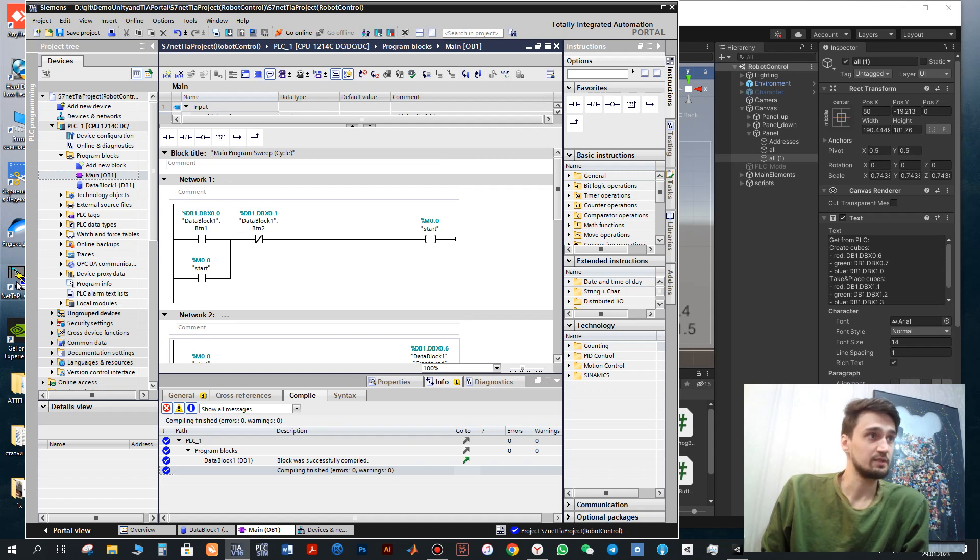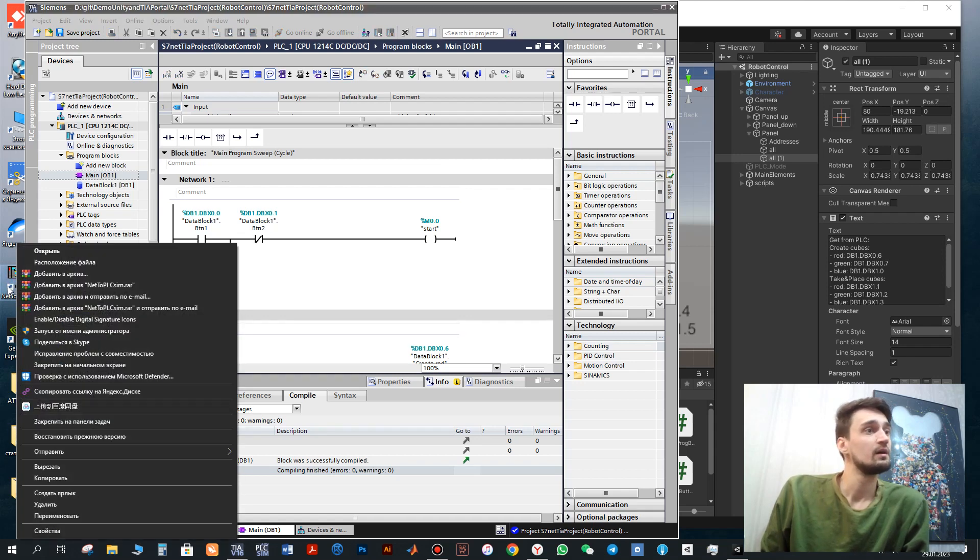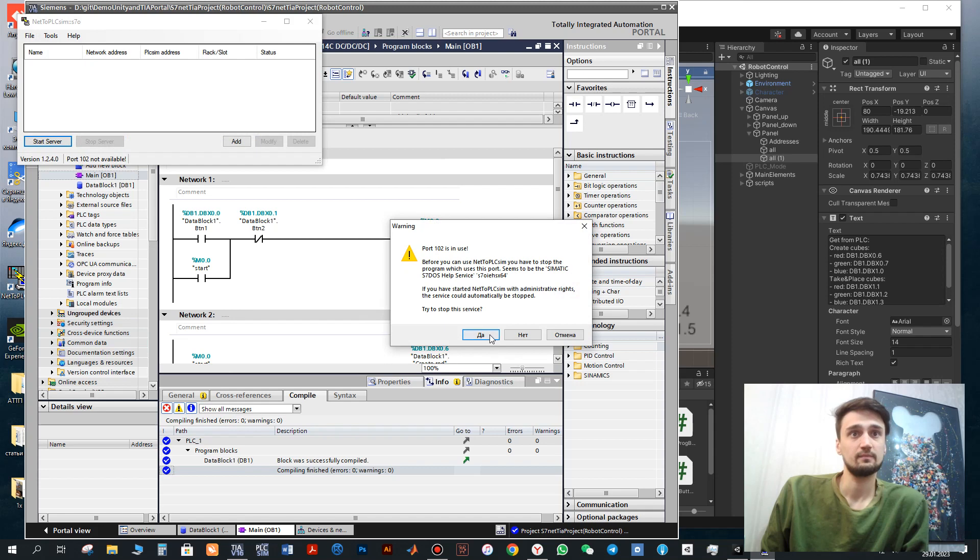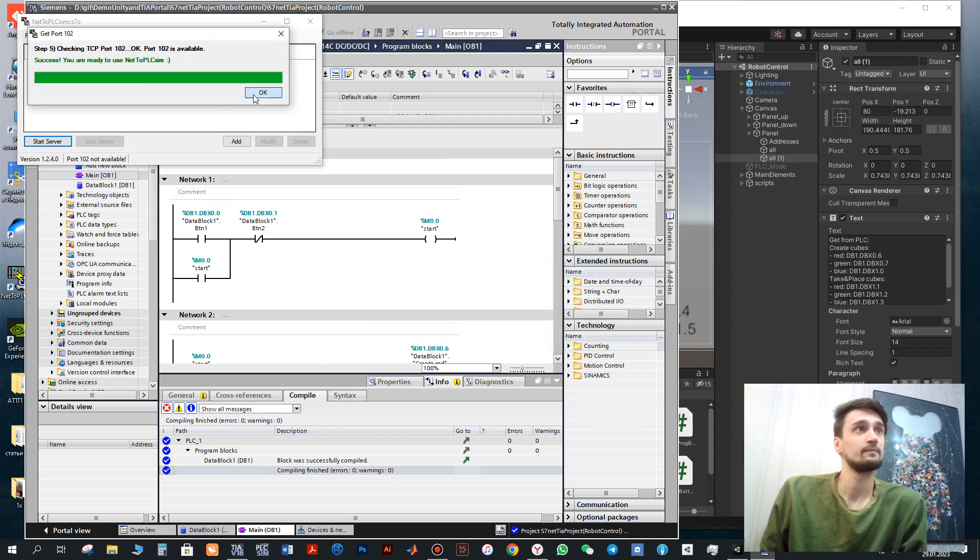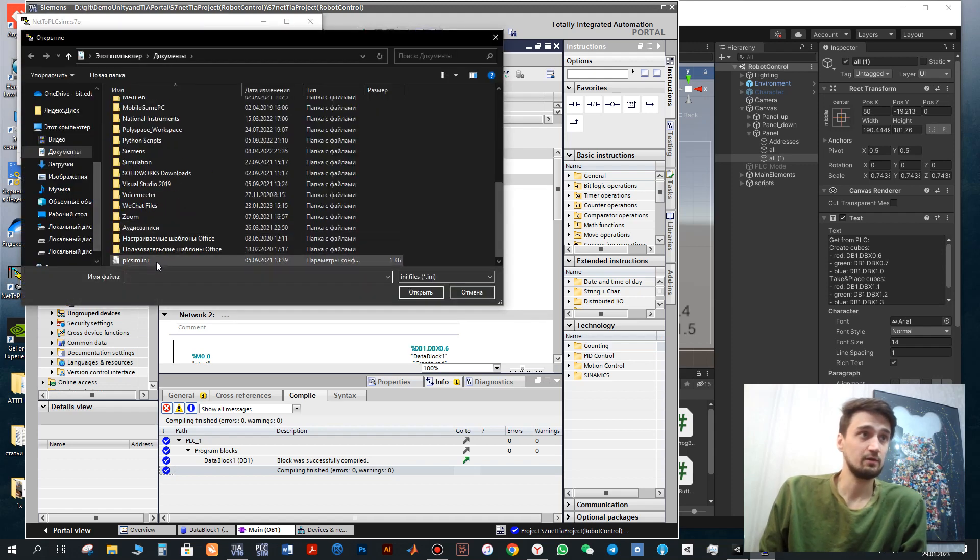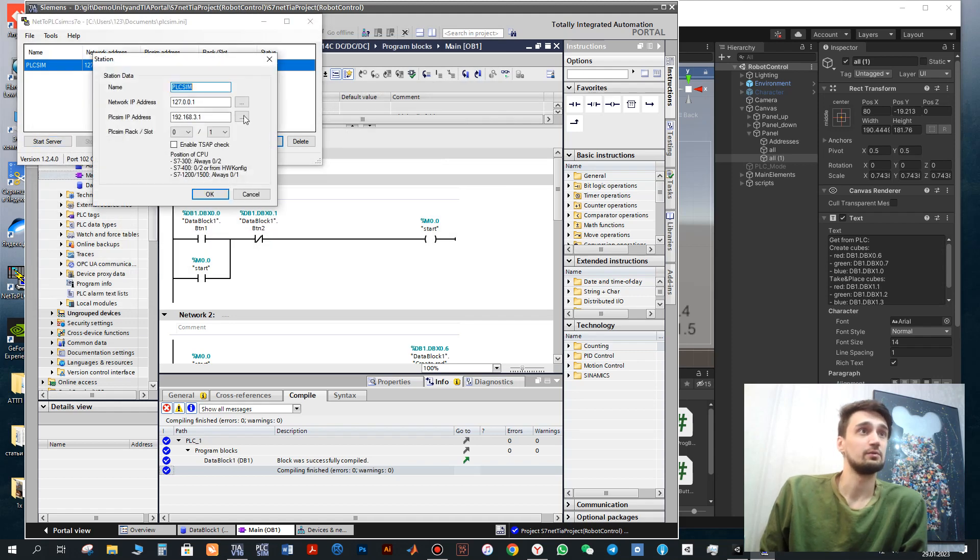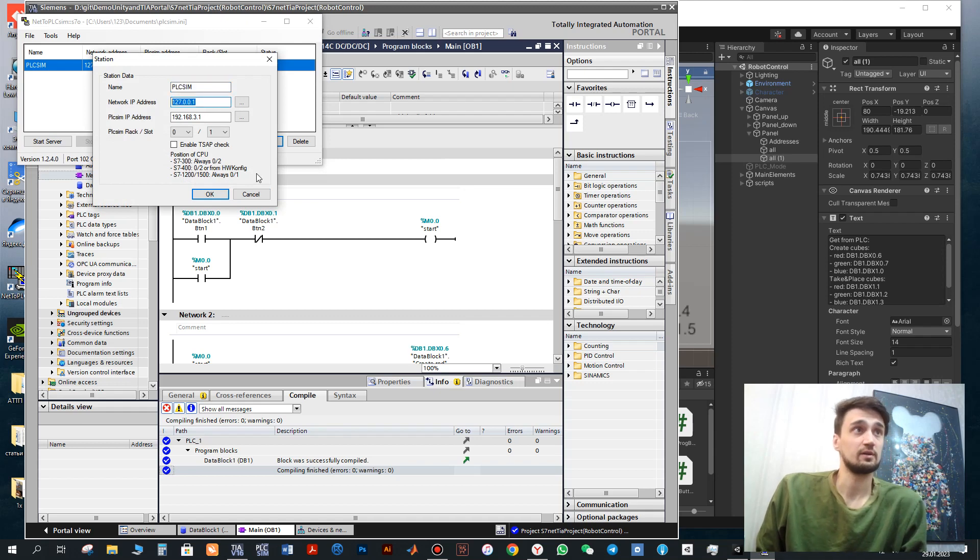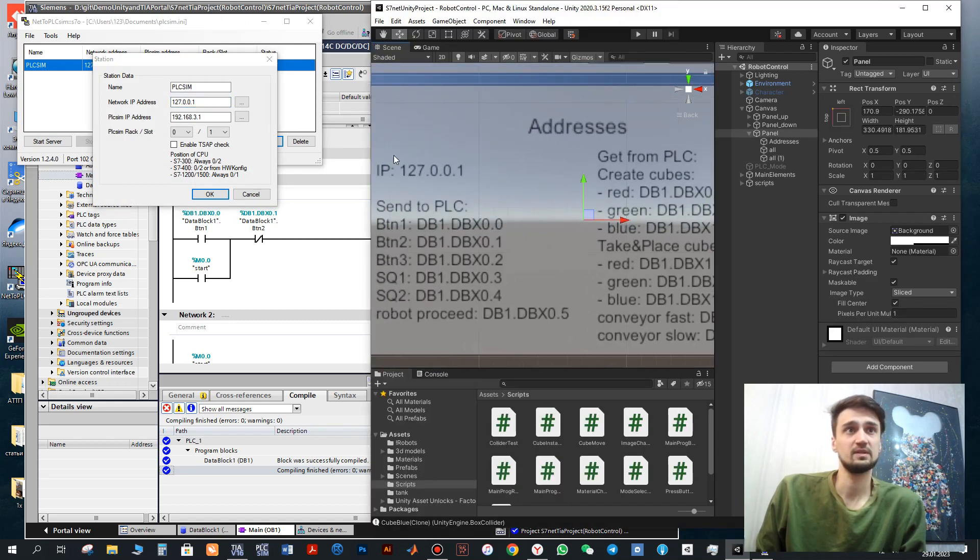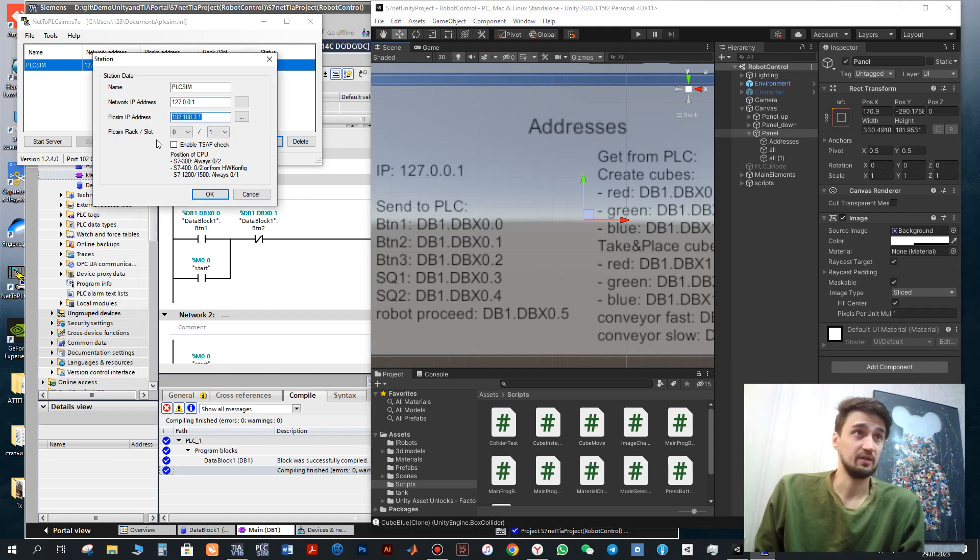What we need to do next is to run the NetToPLCsim program from the administrator. Click yes here. And next open the file or create a new one. So here we need to, for example if you click the new one, here you need to have the network IP address. This is the IP address of the simulator and IP address of the PLC.